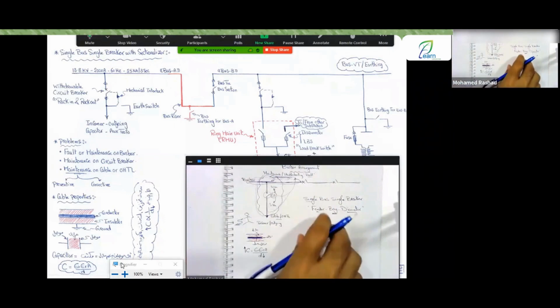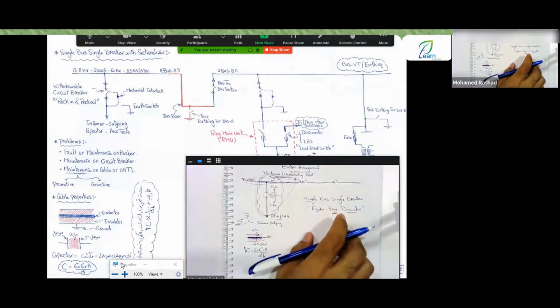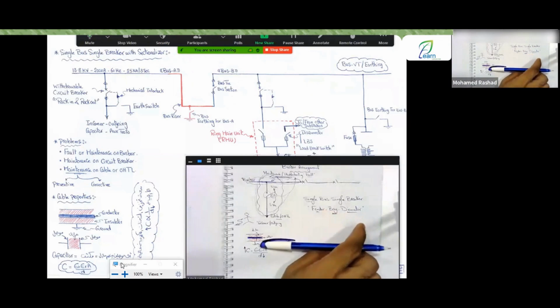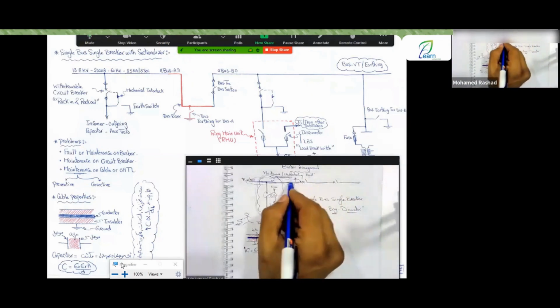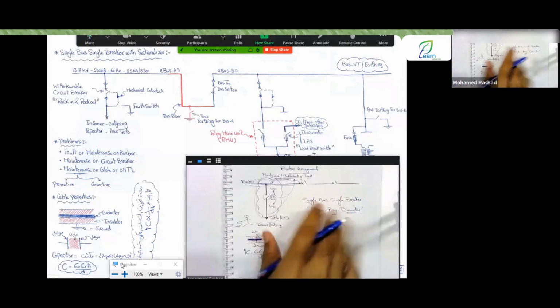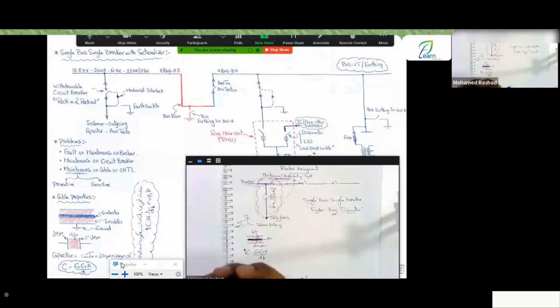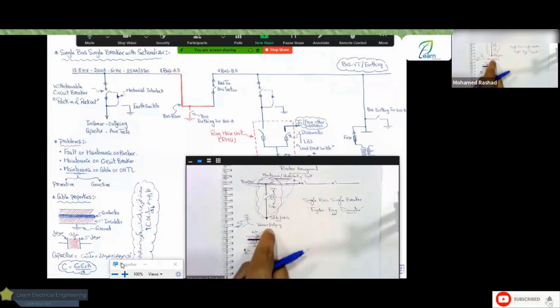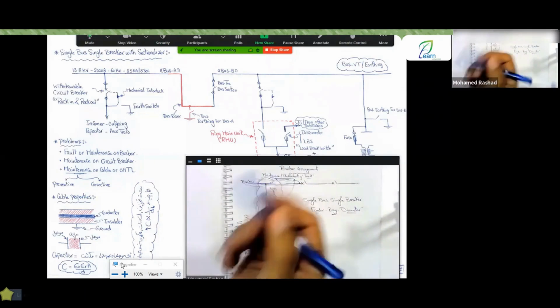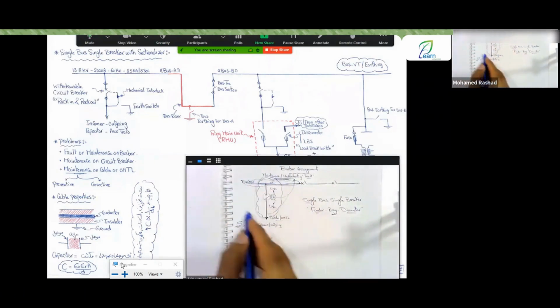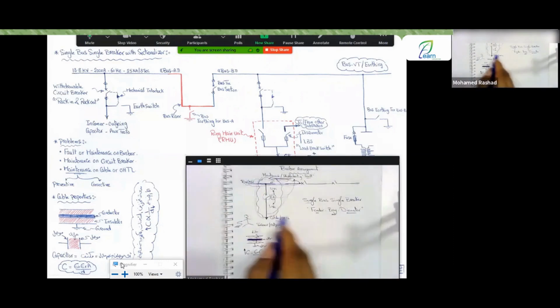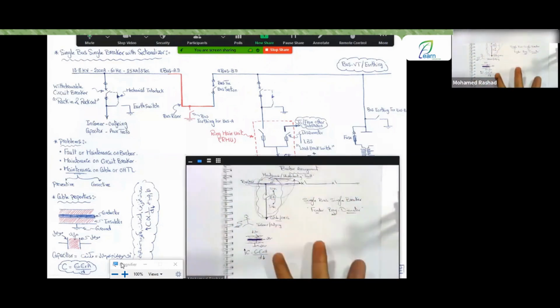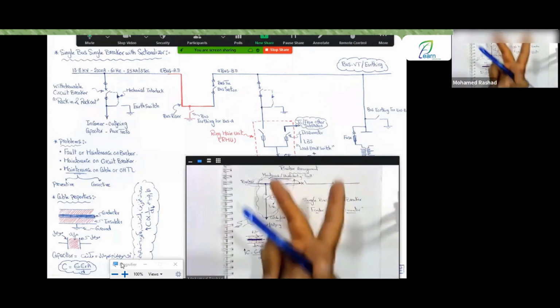I told him exactly that's right. He said to me, all right, and then what, engineer? I told him it's very simple. I said, now, if you don't have maintenance or troubleshooting, but this feeder or this supply, which is the generator or the incoming power to this bar, let's assume it has an issue, or I will perform maintenance on it. It makes sense to do maintenance on it. I would lose all the loads that were connected here when they were all together at first, all at once. I had the 3 sources available, so if one of them failed, the other 2 could supply. I want to achieve the same thing. All right, great. So what will you do?